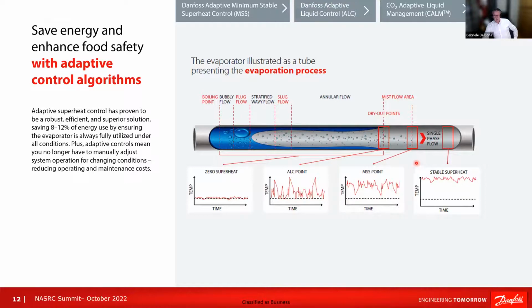not to have liquid going back to the compressor. Usually with a standard controller, what the installer and contractor does is fix a value of the superheat, to make sure that all the bubbles have evaporated, all the fluid has evaporated. Our case controller has a built-in algorithm that is capable of finding out exactly the point and the superheat value at which all the liquid is evaporated, and to keep and maintain it. You can understand that this point can change throughout the day, throughout the operation of the cabinet, because the conditions can change.